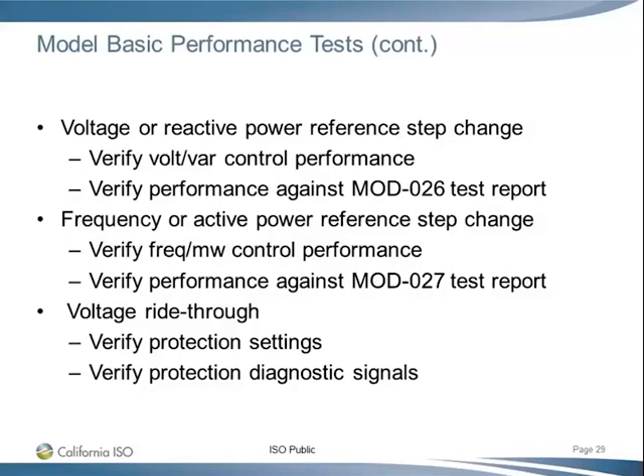Usually the inverters are very fast. If the plant controller slows it down, then for a small disturbance, just a reference step change, it should be governed by plant controller response. So a slow response is reasonable and it's shown in the field test. And a very fast control response in the EMT model is questionable. Also, for the frequency or active power reference step change, we will verify the frequency or active power control performance, then compare that against the MOD-027 test report and see the response time. And a voltage ride-through test is to verify protection settings, verify that the protection treats the inverters properly. Also, we want to see the protection diagnostic signal when the generator is tripped. There should be an indication why it is tripped.